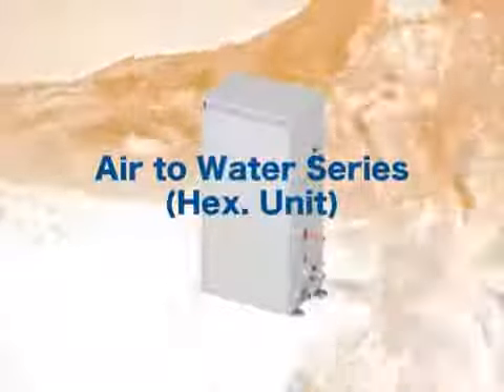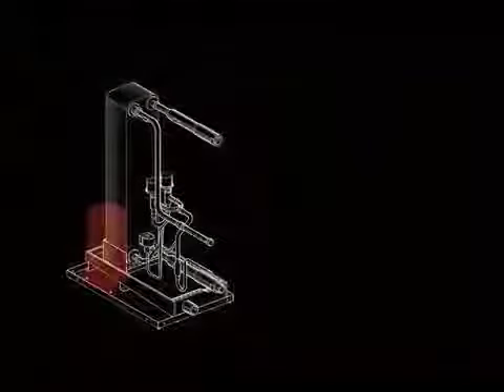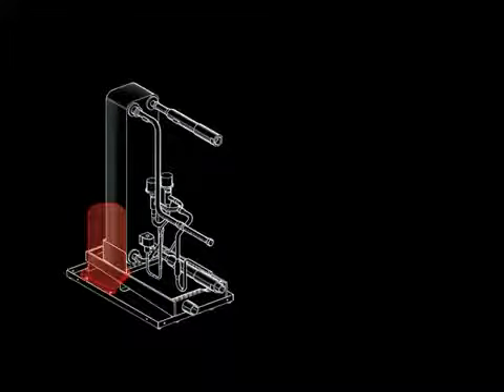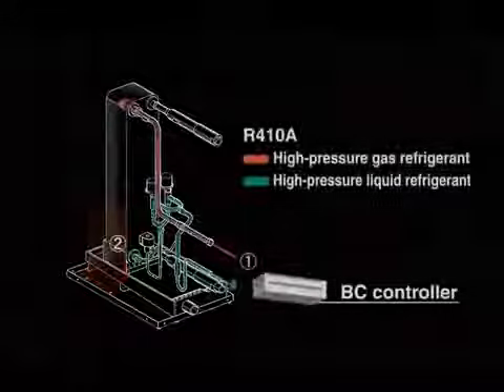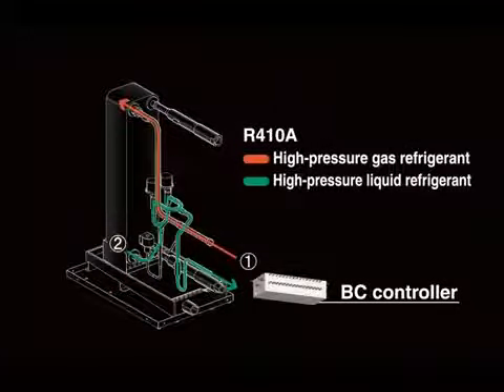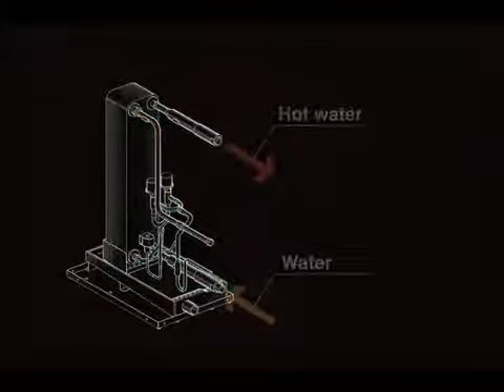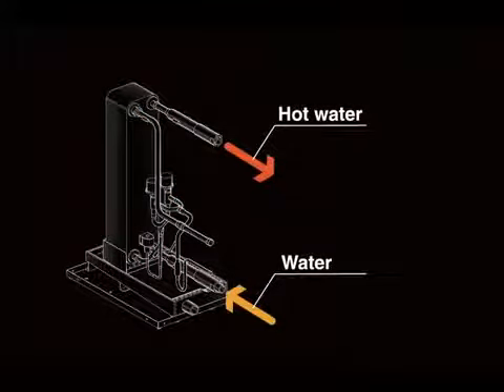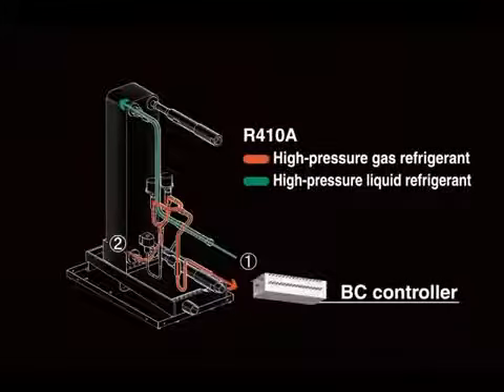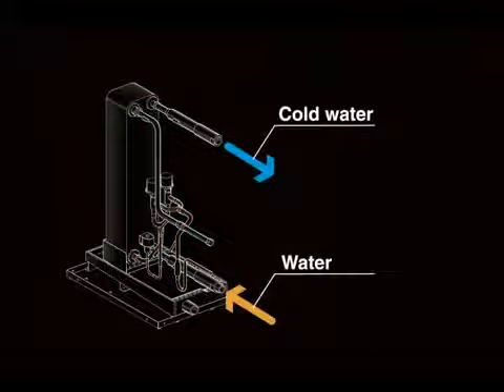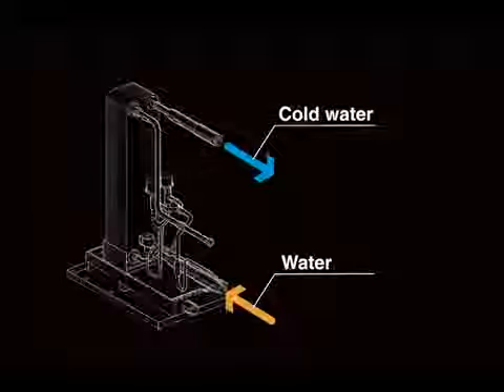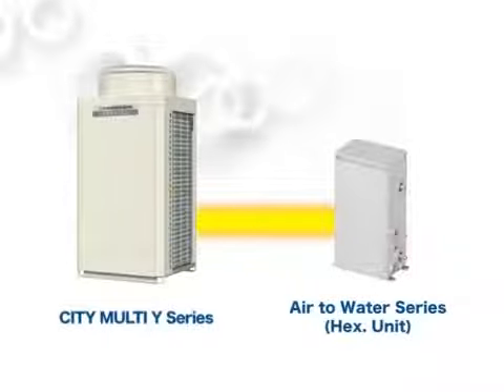Heat exchanger unit is connected to BC controller with refrigerant pipes and to the water tank with water pipes. Heat exchanger unit is not equipped with the compressor. To supply hot water, water entering the heat exchanger unit is heat exchanged with R410A refrigerant delivered from BC controller. Heat exchanger unit offers hot water to a maximum of 45 degrees Celsius and cold water down to 10 degrees Celsius, which is suitable in supplying water to fan coil units. Heat exchanger unit can also be used with our Y series, but there will not be a heat recovery operation.